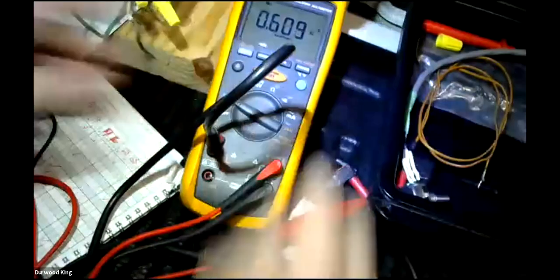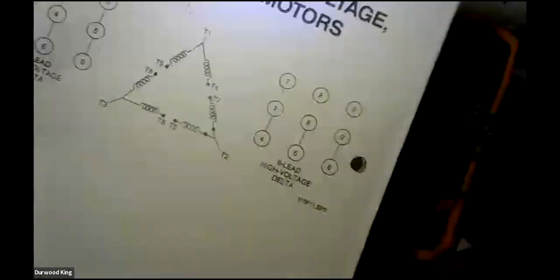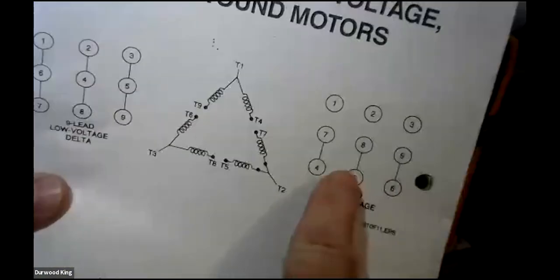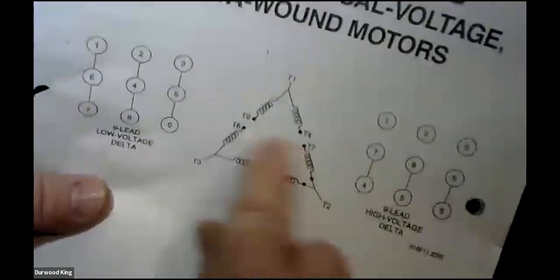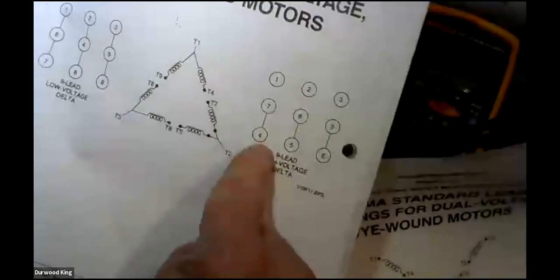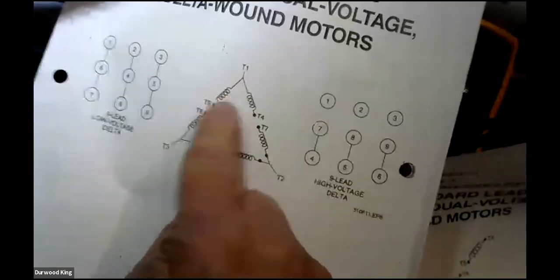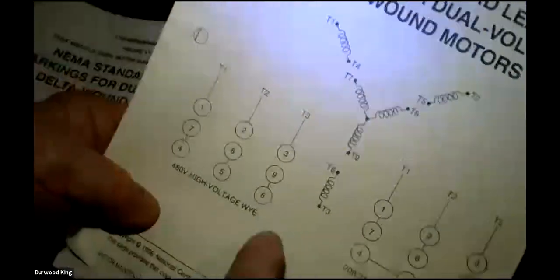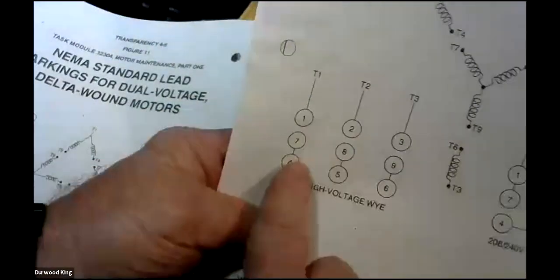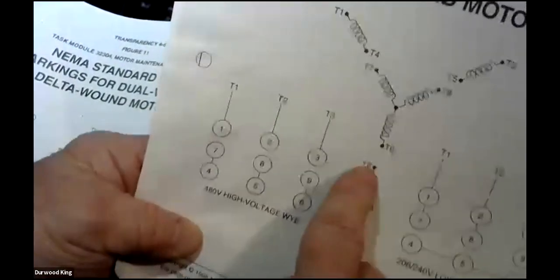So now, the only other thing that I'll mention, and this will be enough in closing, is this. If you had a Delta motor at high voltage, it's the same numbering as a Y. If you compare, it's 4 and 7, 5 and 8, and 6 and 9 if it's high voltage, which puts them in series. It makes them in series whether it's a Y or Delta.